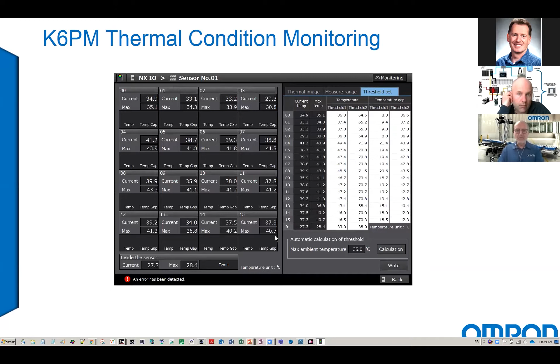Let me show you the actual camera and the size. This one here, yeah. This is the section it was looking at, and this is the actual camera that's mounted on a magnet here on the side of this little handmade bracket. I did that because if I close the panel, you won't see inside, obviously. By putting this back up here in the right place, it should be looking at the proper section of the software. Let me do this again, like this. You can see that if I move it, the actual temperature image will change, and I can see a different aspect of your control panel. Give it a few seconds, and it's going to update and then show you a new area.